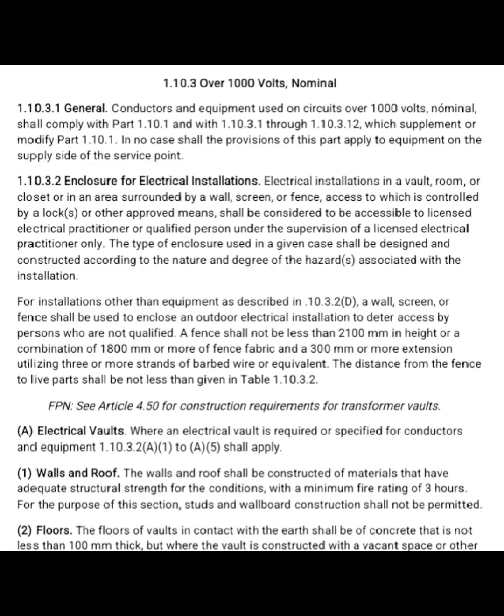For installation other than equipment as described in 1.10.3.2d, a wall, screen, or fence shall be used to enclose an outdoor electrical installation to deter access by persons who are not qualified. A fence shall not be less than 2100 mm in height, or a combination of 1800 mm or more of fence fabric and a 300 mm or more extension utilizing 3 or more strands of barbed wire or equivalent. The distance from the fence to live parts shall be not less than given in Table 1.10.3.2. See Article 4.50 for construction requirements for transformer vaults.